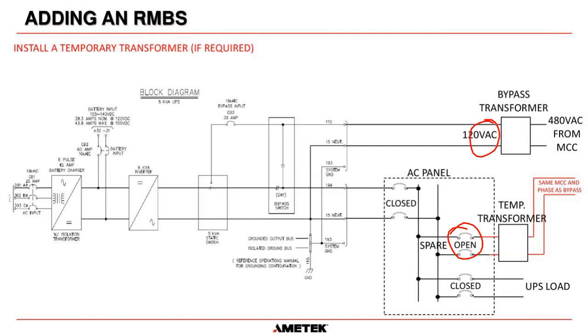So as long as we know this is A phase and this is B phase, let's just say, we need to go to the same MCC and pick off A phase with respect to B phase there, put it into our temporary transformer, and therefore we're going to get 120 volts out here. This one here should be in phase with this one here. But I'm going to show you how to check that before we go any further.